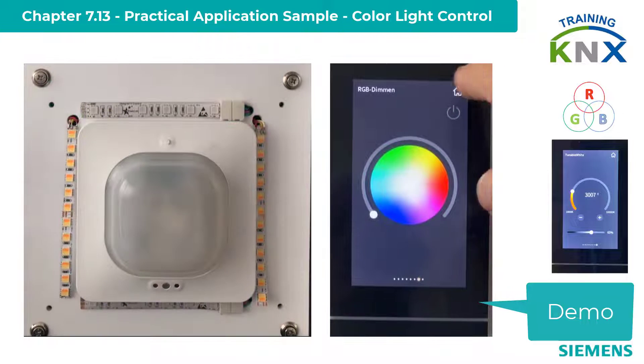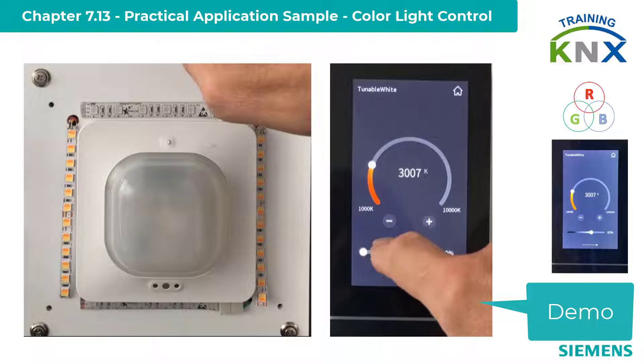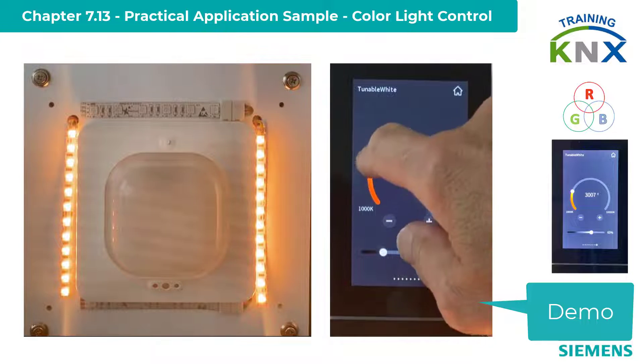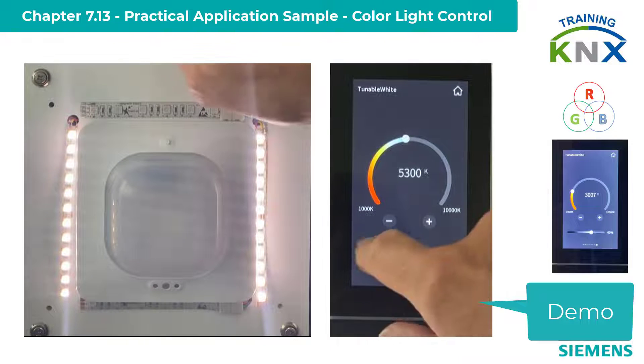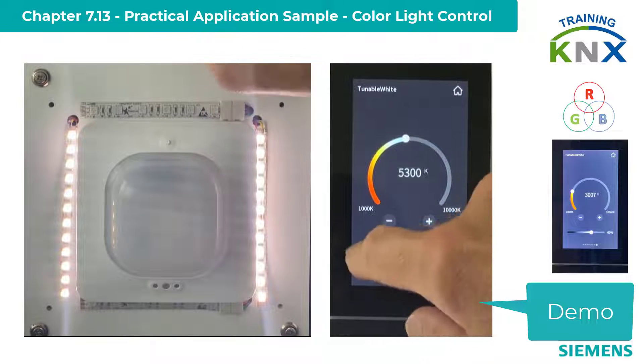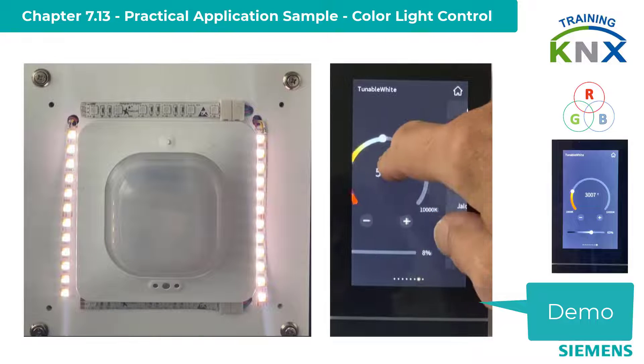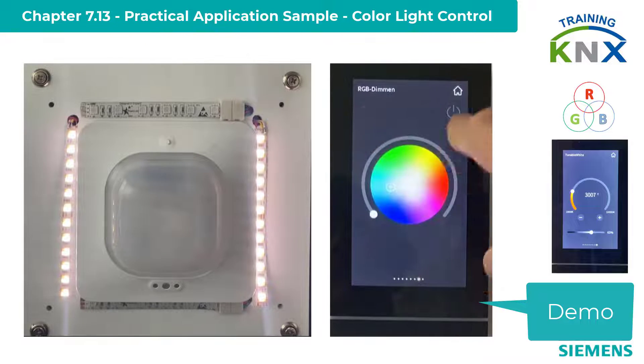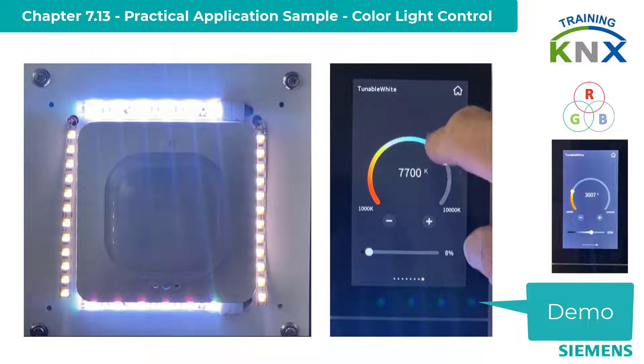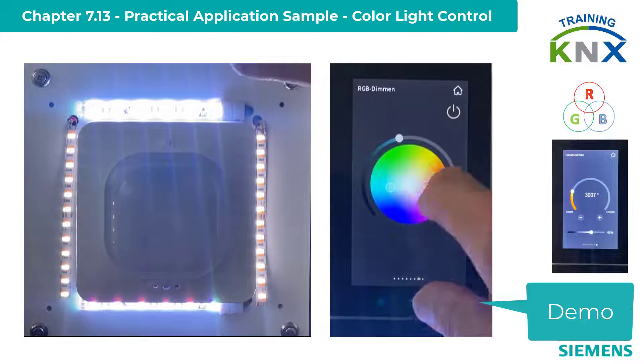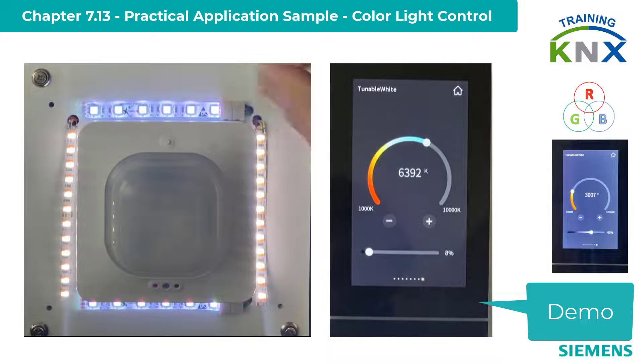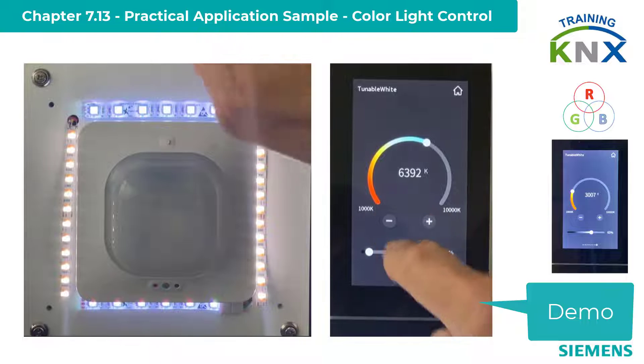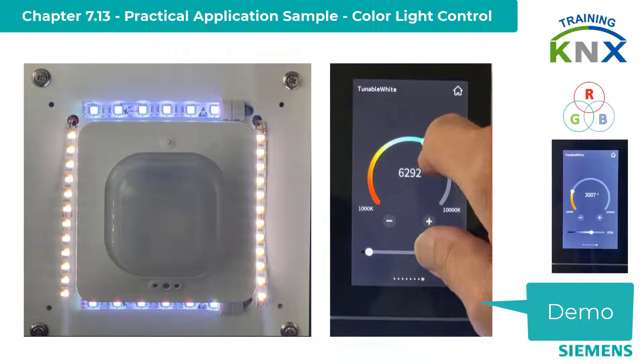Now to the tunable white page. Here there is a slider for brightness and a circle for color temperature. The color temperature scale is fixed and ranges from 1,000 to 10,000 Kelvin. Therefore, the feedback from the DALI gateway after adjustment automatically ensures that the two limit values — here 3,007 and 6,492 Kelvin — are neither undercut nor exceeded.